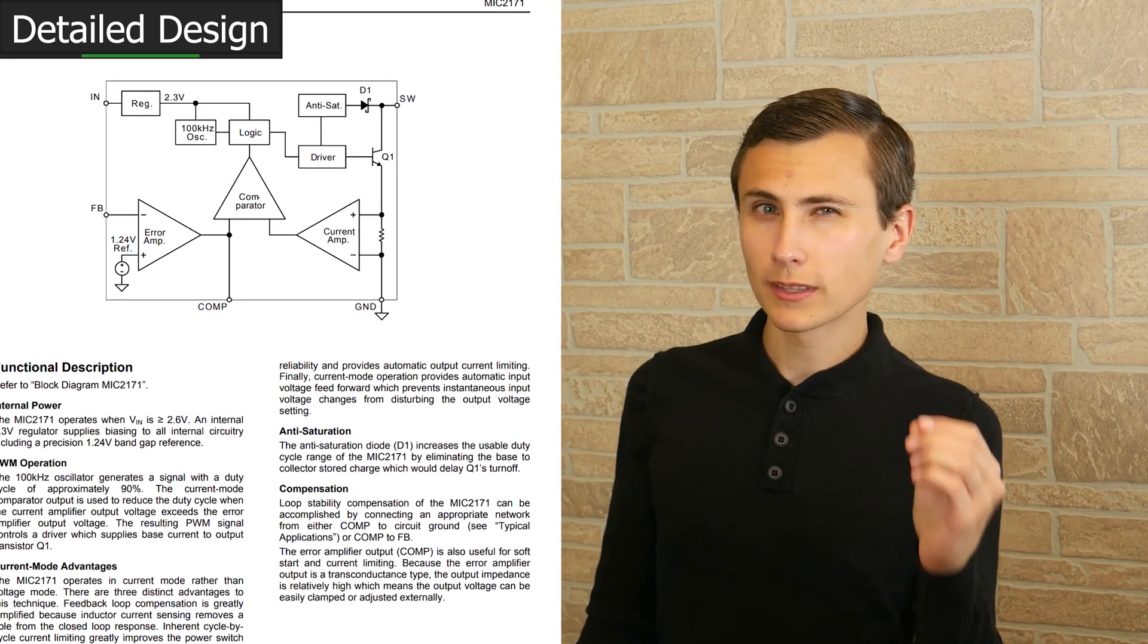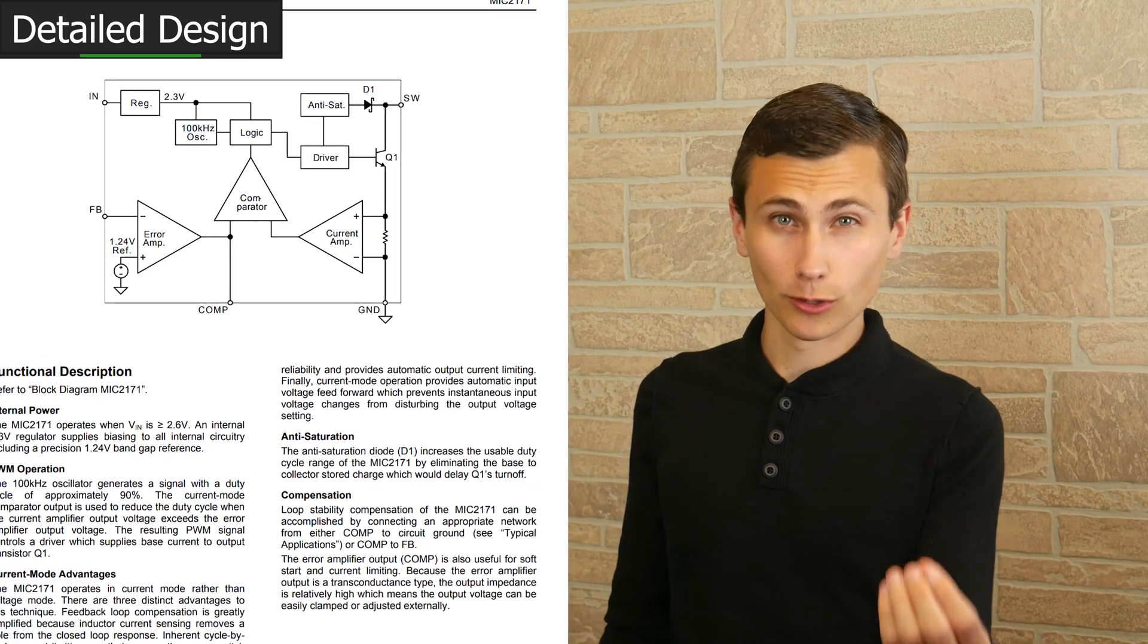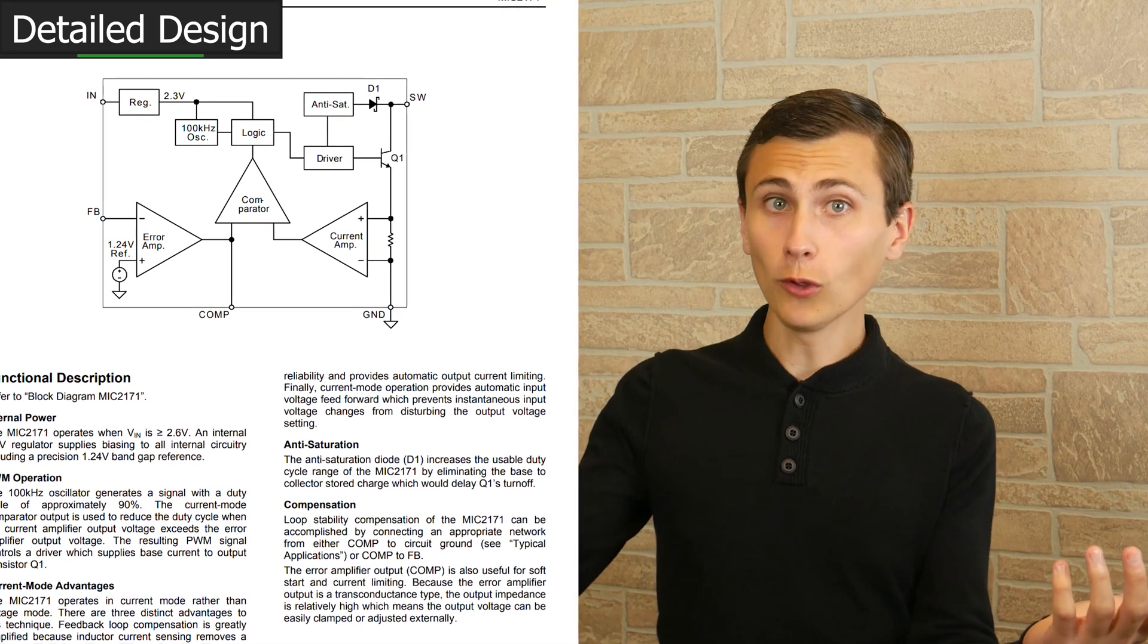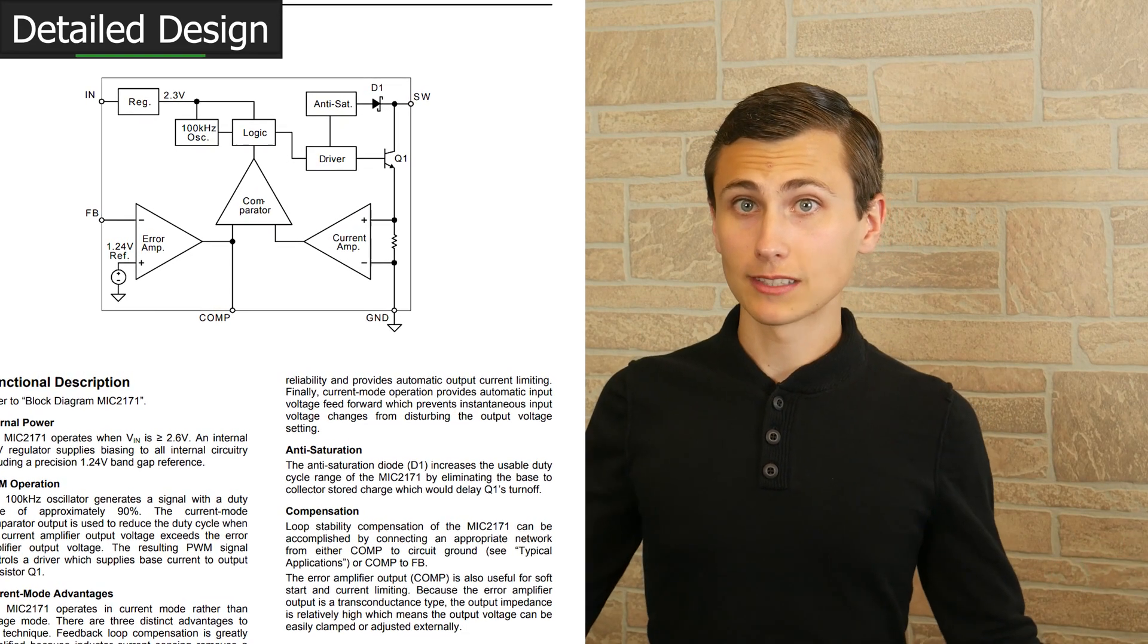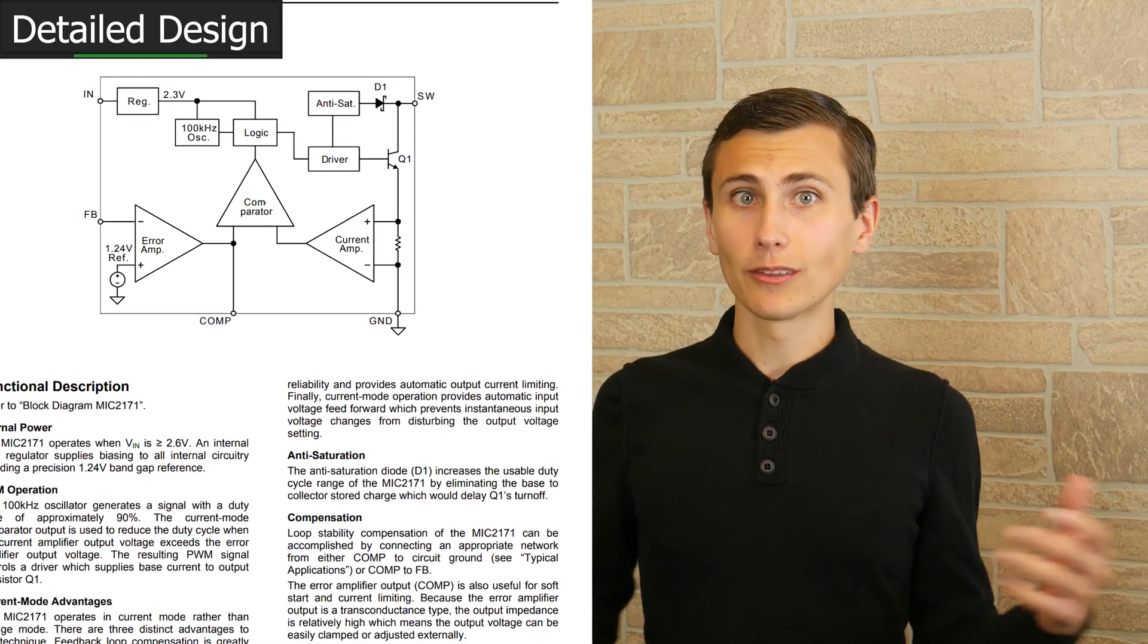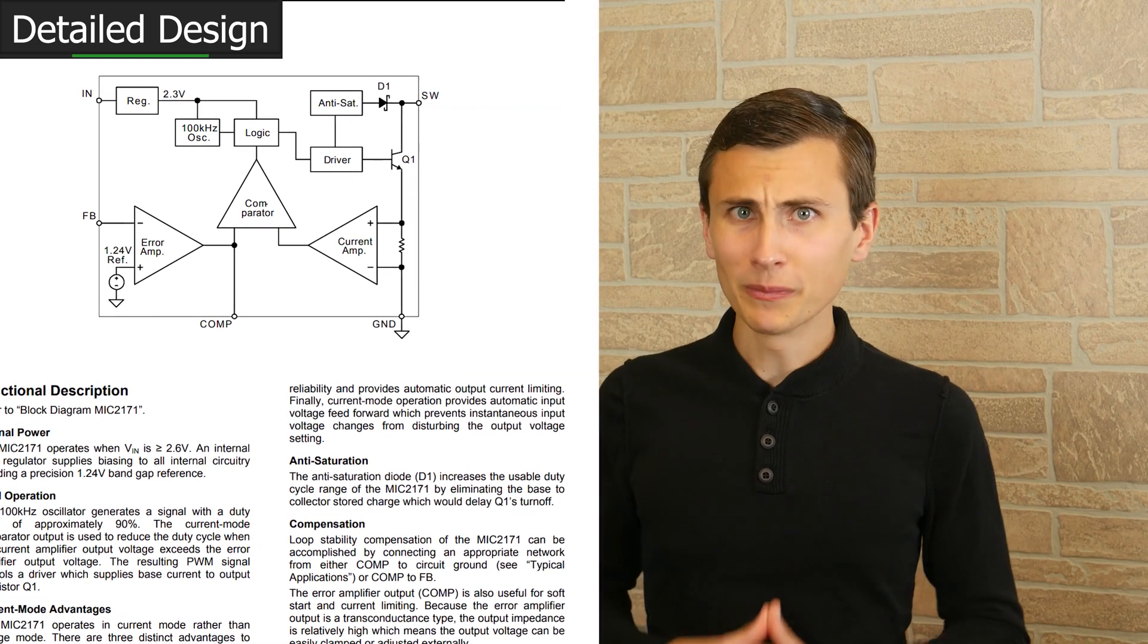Can you see where I'm going with this? Basically, we just take this converter, set the output voltage to our float voltage, 54.4 volts. The internal current limit cuts out at 2.5 amps at every cycle, and there are internal thermal protections as well. Basically, the current limit will just happen automatically when the batteries are well below 55 volts, and then the charge current will linearly taper from around 2 amps to around half an amp as the battery voltage increases. That last little bit is where our design will really shine. Again, a graceful transition from current limiting to voltage regulation as we enter float charge mode.